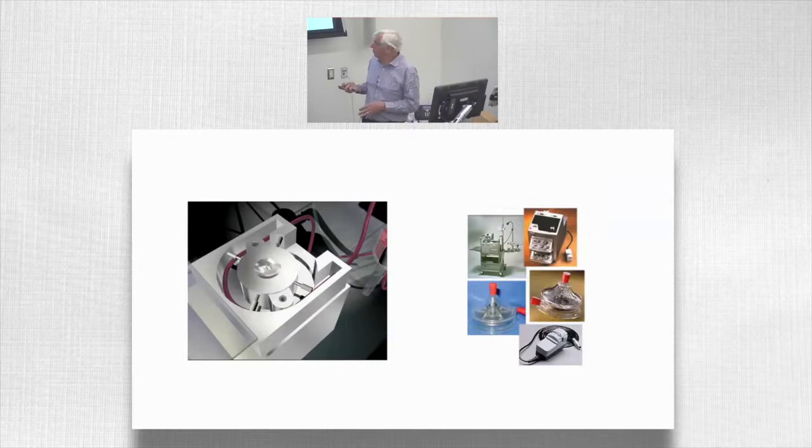So they used to use a roller pump, which now is sort of obsolete technology for support outside the operating room, still used in the operating room. And we're now using something like a constrained vortex or this pump head here, which is a much simpler device, which has less complications.